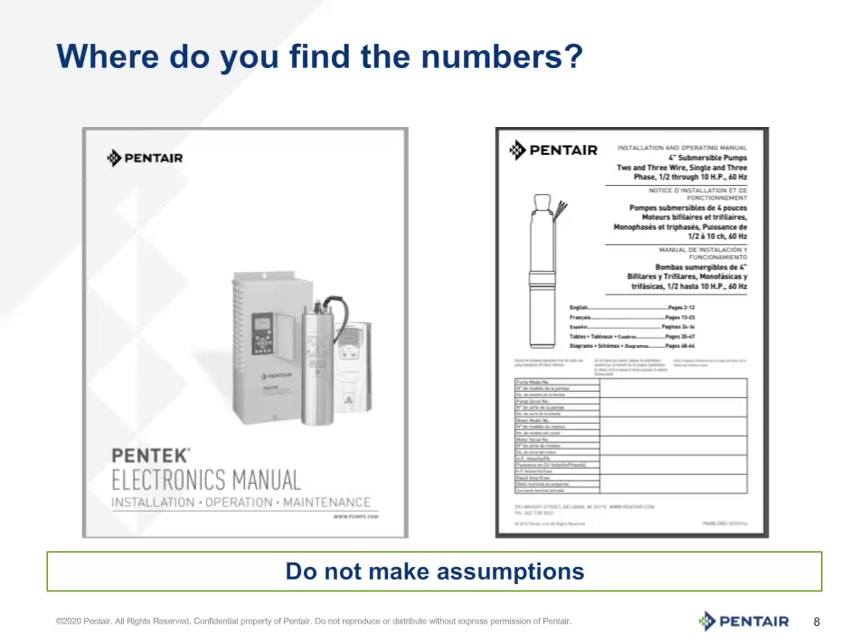Where do we find the data to understand what this ohm reading means? The meter will give you a number — it may range from 0 all the way to OL, or out of limit, depending upon the meter. All motor manufacturers print, in some form, the acceptable range of ohms readings for their product. At Pentair, we offer the PN 793 electronics manual as well as the owner's manual that will have specific information to the product installed or purchased. We are looking for the motor winding information based upon the model number of the motor installed in the system. It is often easier to find the information in the owner's manual because it lists only the applicable ohms reading rather than the catalog that would list the entire offering.